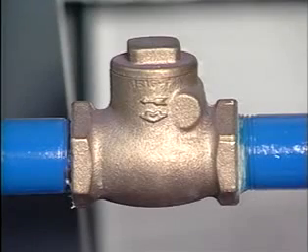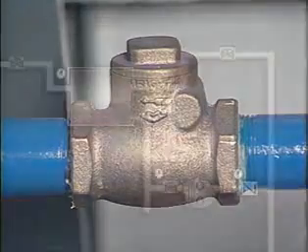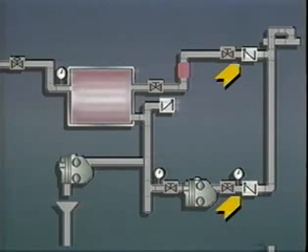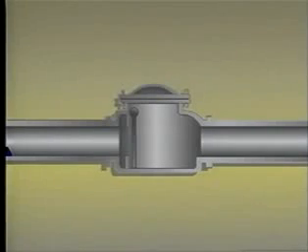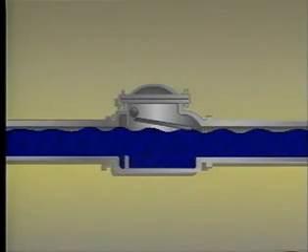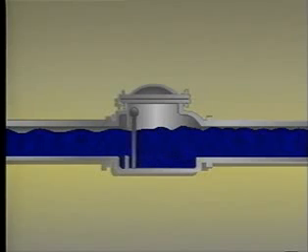Sometimes check valves can produce hydraulic shock. Swing check valves are often used to prevent liquid being drawn into spaces that are subject to intermittent vacuums. They are also applied to prevent backflow from elevated systems when adequate pressure to raise the liquid cannot be guaranteed. In either case, the acceleration of the reversing column of liquid may be quite high. If the swing length of the check valve is sufficient, the column will build enough inertia to cause hydraulic shock in the time it takes the valve to slam shut.